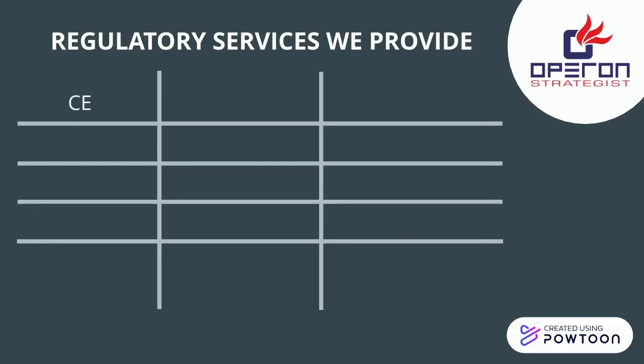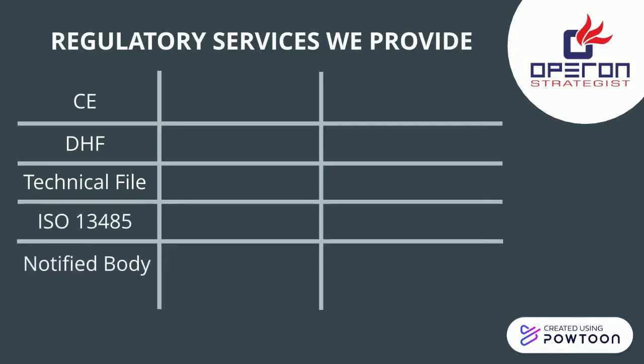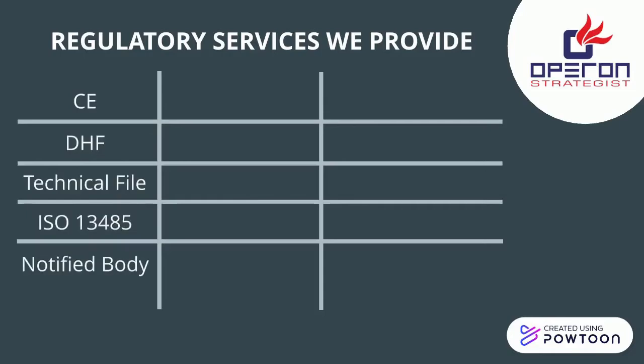CE. To acquire a medical device CE mark, the manufacturer must document the product quality, safety and performance. DHF. The preliminary requirement is the design history file DHF. Technical file. This creates a groundwork for the creation of technical file. With this we cover the product-specific requirements for CE marking. From the facility point of view, ISO 13485. ISO 13485 certification is a mandatory requirement for quality management system. Notified body. Submission of all the files are done to the notified body, who then audits the complete applications and certifies the product.